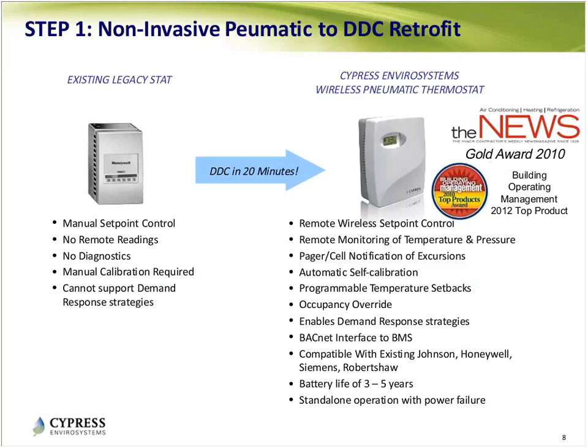So it's a lot of effort to change them over. Now, once you upgrade this device from the pneumatic to this wireless pneumatic thermostat, it does a whole bunch of things. You have remote control, remote sensing of temperature and pressure, and BACnet connection to your building automation system, so you can see it on your Andover, Schneider, or Siemens systems.